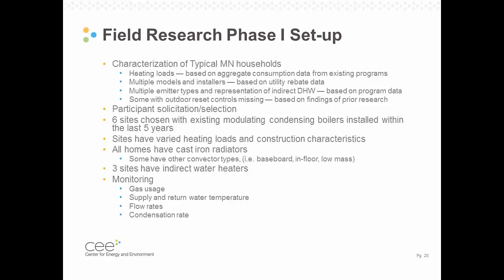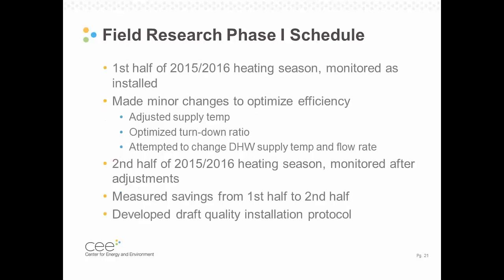And then as far as the monitoring package, we did gas usage analysis, supply and return water temperature rates, flow rates, and then condensation rate, so that we could study all of the performance. For the first half of the 2015-2016 heating season, we monitored those 6 sites without any intervention by us. And then after we had a good set of data for those systems, we made some minor changes to try and optimize efficiency. We adjusted supply water temperature.